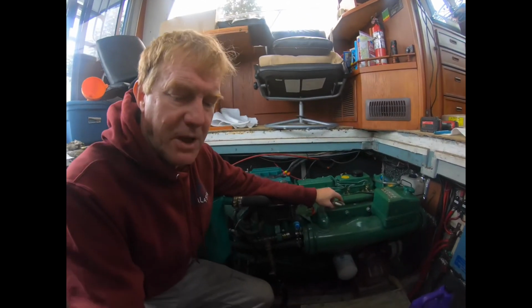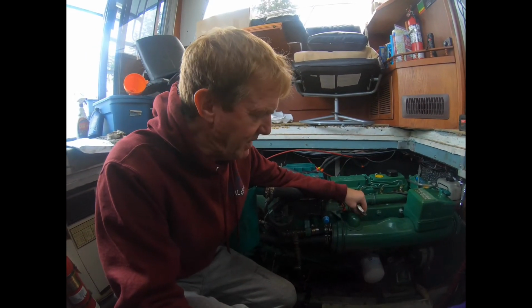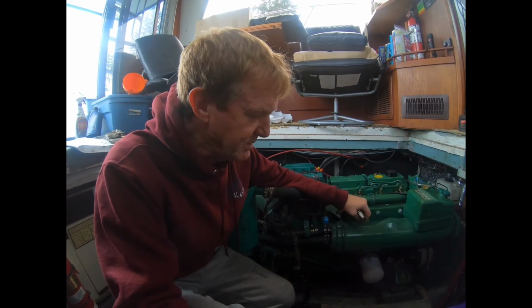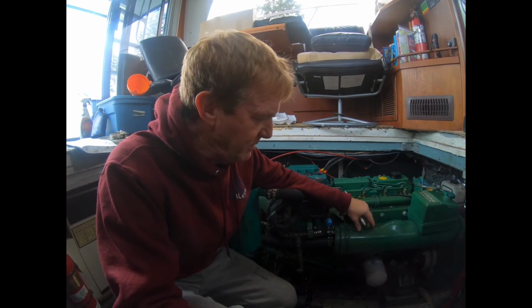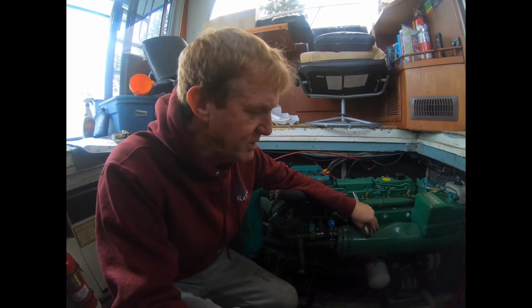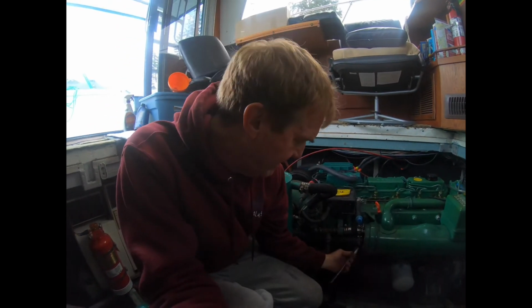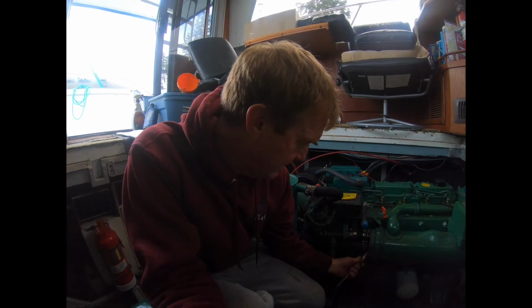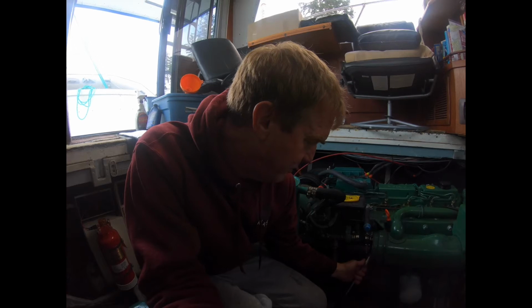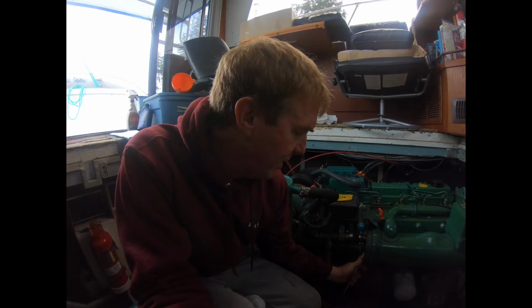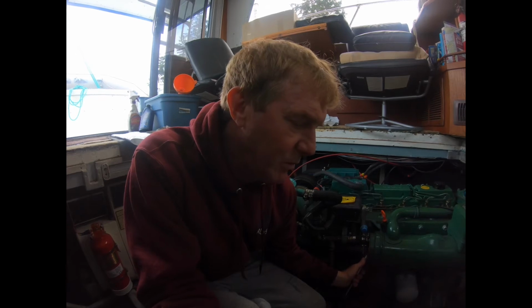A basic phenomenon on marine applications is you can get what they call electrolysis. That's electrical stray current in the salt water going through your heat exchangers, which can eat the metals away. So what they've done, at least on this motor or these motors, is they've put a zinc anode in there, which the stray current will eat, or break down, instead of your heat exchanger.